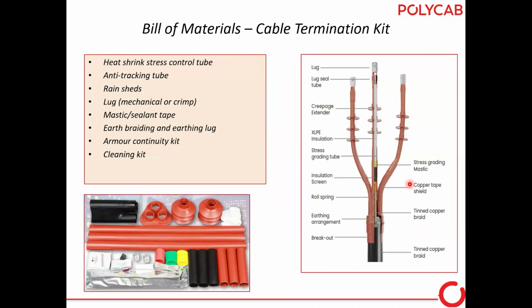Again, like we saw in the joint, different components, here the termination also has different components. So heat shrink, but function-wise, it's similar to the joint. The components are heat shrink, stress control tube, anti-tracking tube, rain sheds, lugs, mastic sealant tape, earthing braid and lugs, armor continuity, and cleaning kits. With these components, we do our terminations.